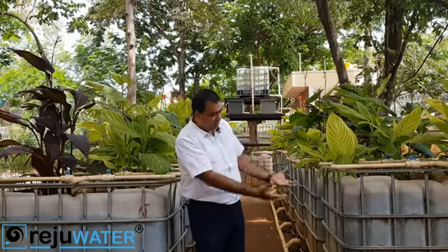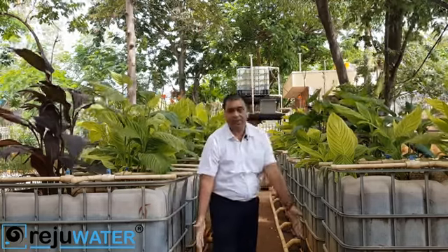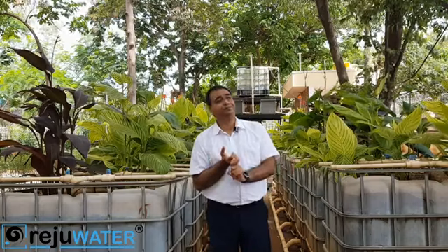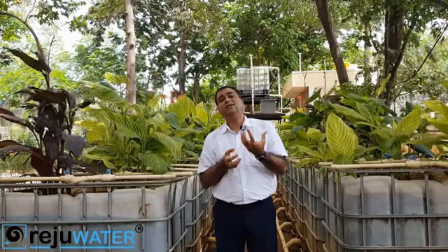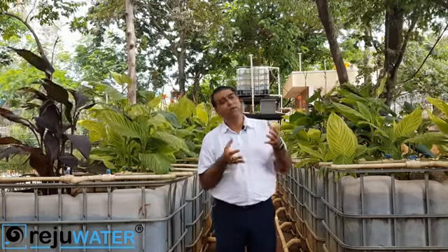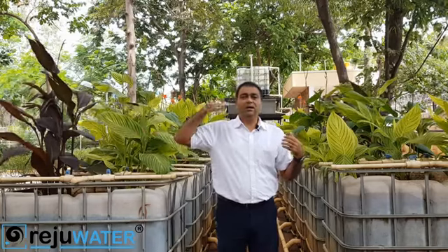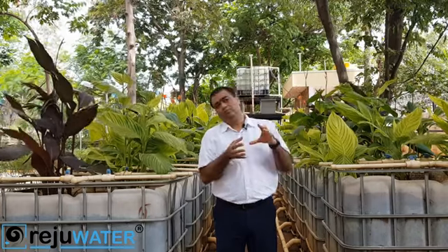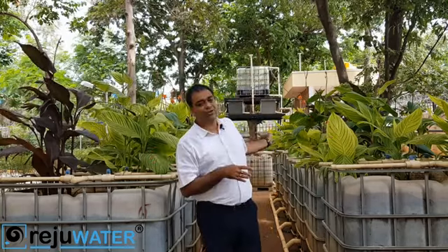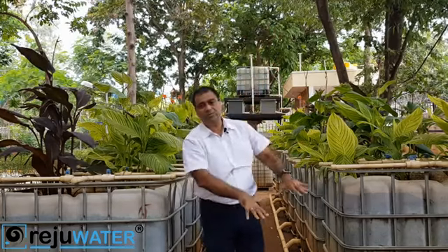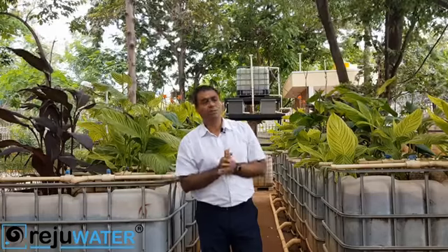As it percolates, the clean water comes down through these pipes, and that is the water that we reuse for flushing, gardening, car wash. Now, if you have visited any sewage treatment plant, you will see 3-4 things which are unique with any electromechanical technology. One is you will have a series of tanks: a collection tank, equalization tank, aeration tank, clarifiers, then filtration. In our case we just have one collection tank and one treated water tank. The water from the collection tank goes to the overhead tank, comes down through these modules and gets collected in the treated water tank, and from there it is sent for all kinds of reuse purposes.